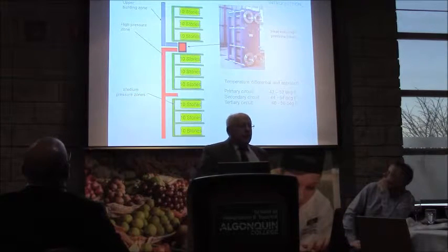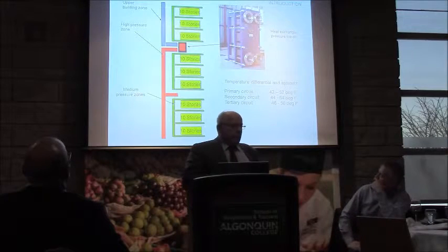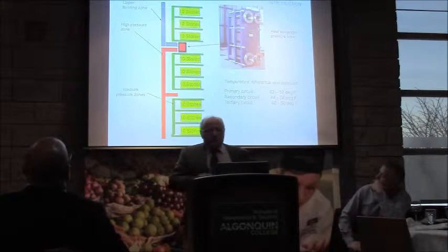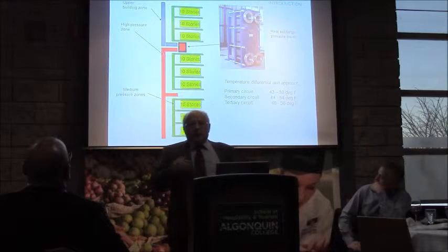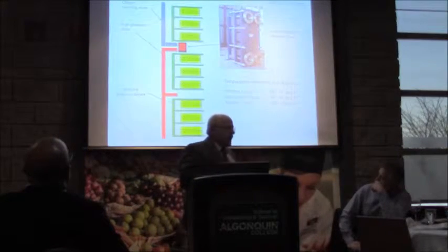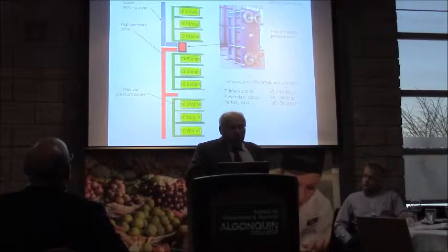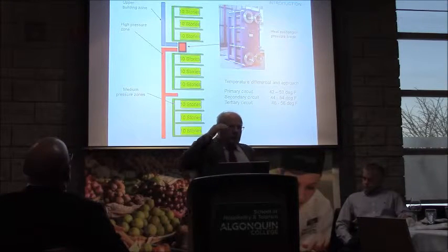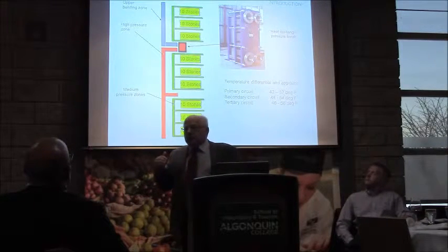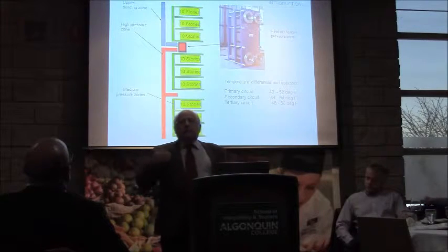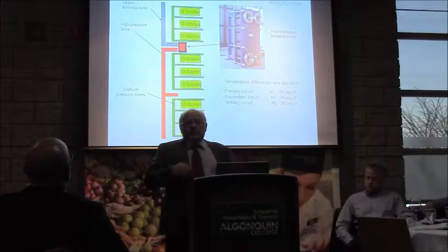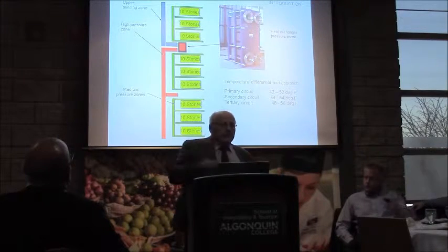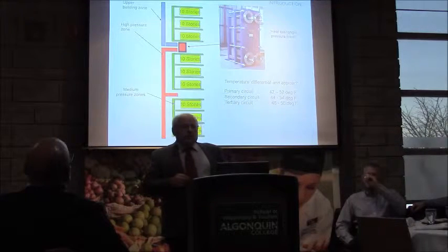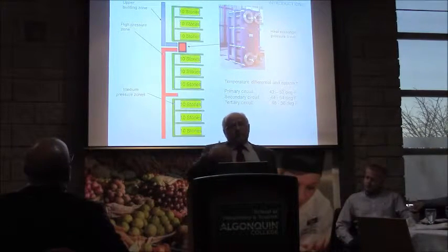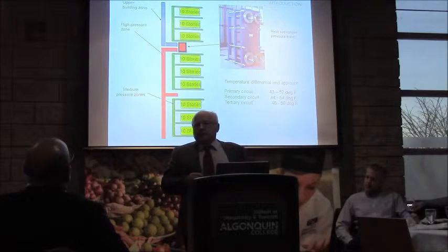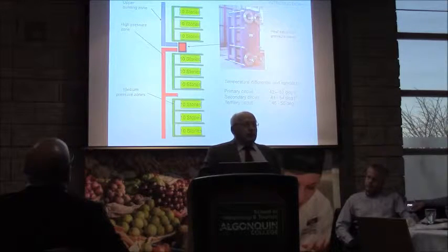As we move beyond the limits of the equipment we want to be dealing with, we put in pressure breaks. In a closed system, the heat exchanger is the typical pressure break that we would have. And the place where that pressure break occurs really depends on the economics of providing high pressure systems. Is it cheaper to buy very expensive piping or very expensive infrastructure, or is it cheaper or available to have mechanical rooms more often in the building and switch over to a lower pressure regime?